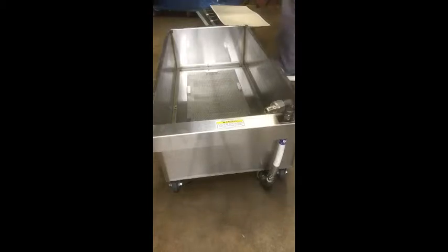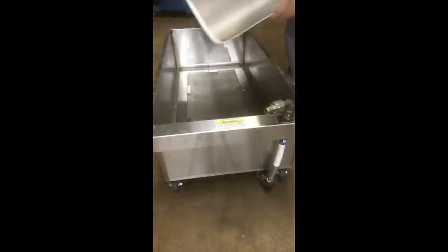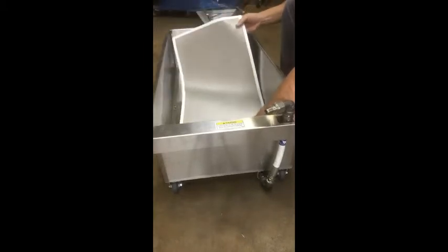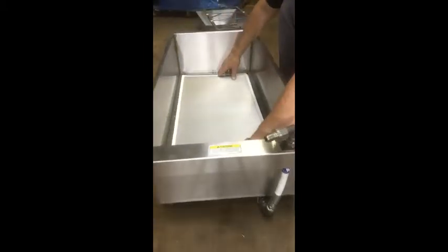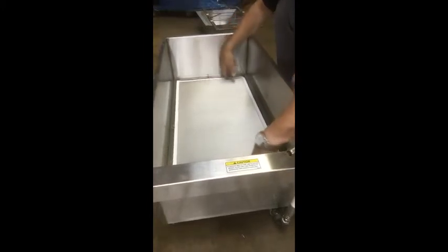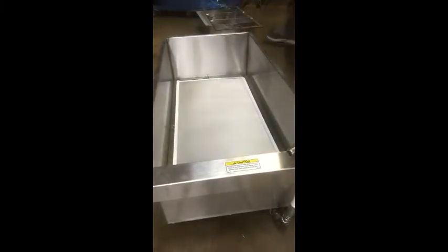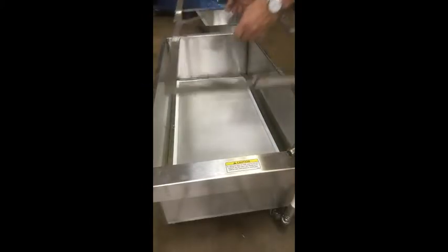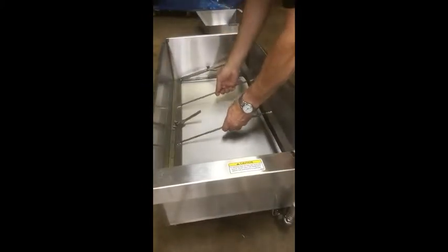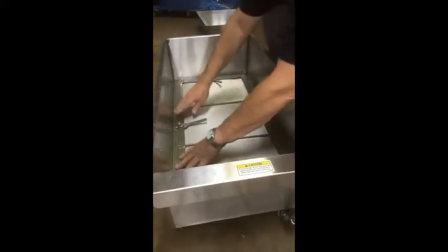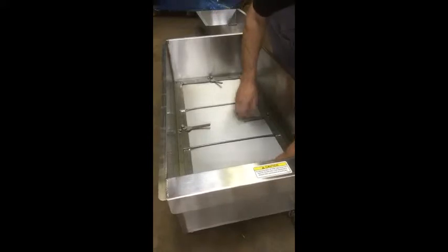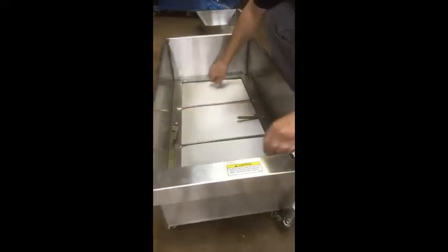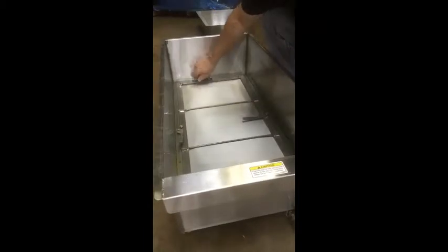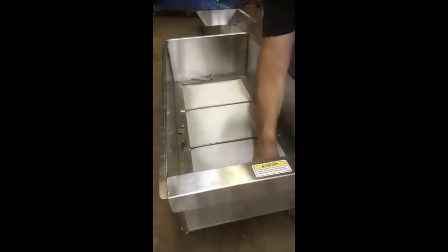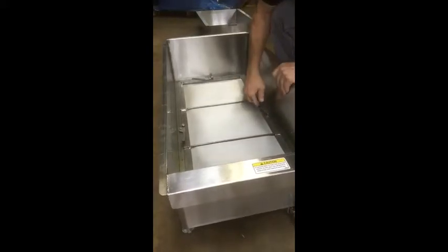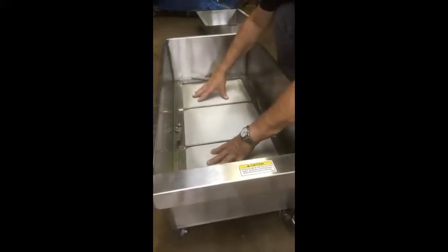If setting this up for the first time, you have a filter screen. This is a reusable filter screen instead of filter paper, and you would put that down in there like so. Make sure that it is within the confines of the frame. Then we have what we call a hold down frame. This hold down frame then sits atop of that to make that sealing edge, that white sealing edge, seal. And then we lock the 4 handles in, pushing down slightly. All of those are locked in place. Now any sediment that goes in has to go through this.